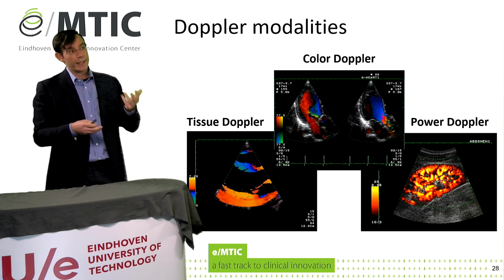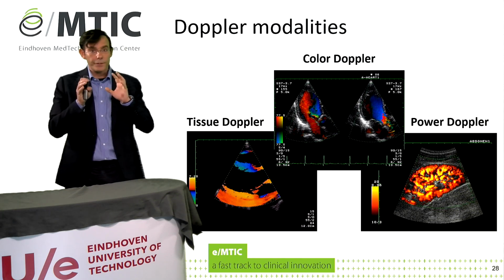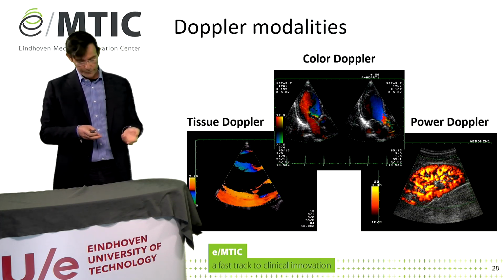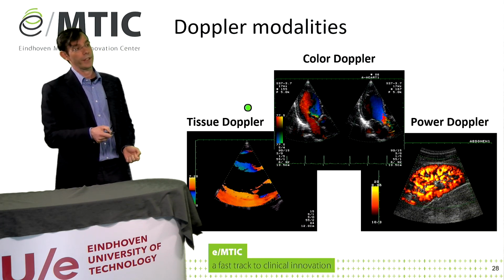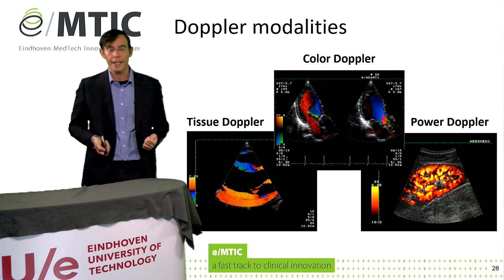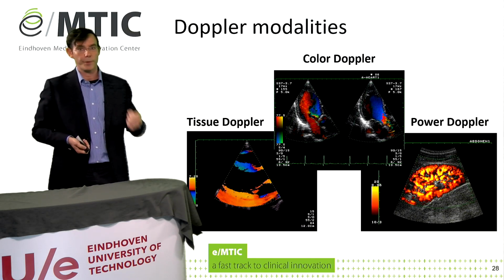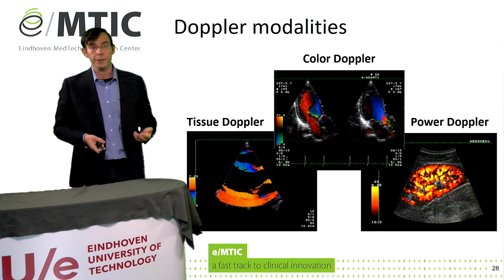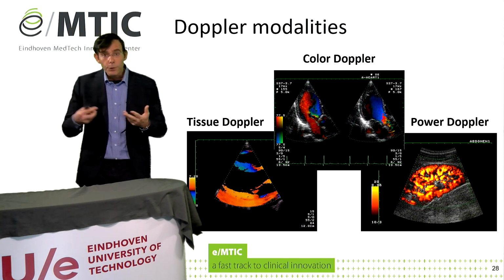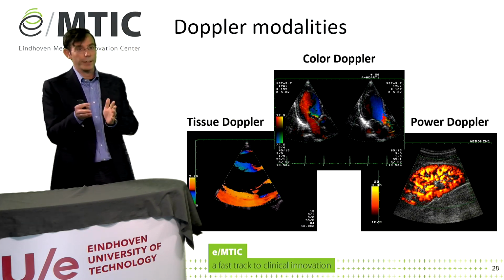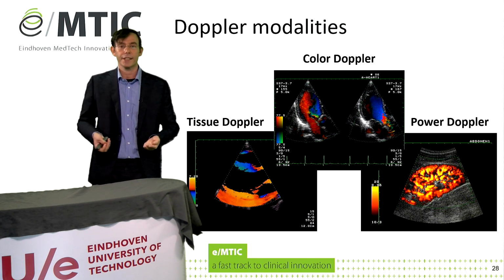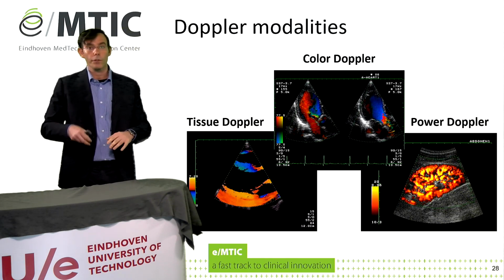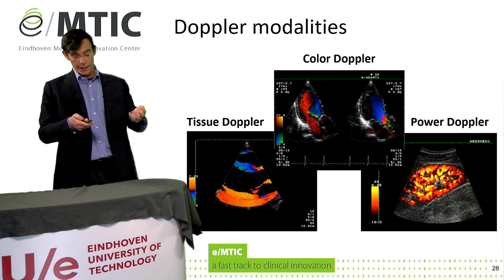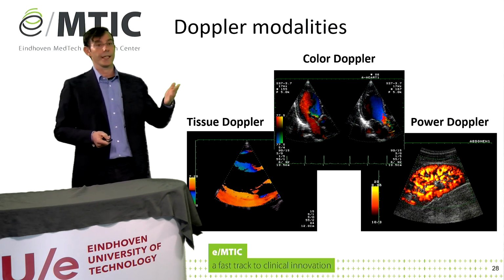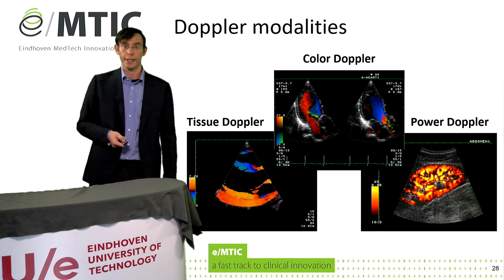You can also set up the filters in a different way and therefore focus on slow-moving structures, like for instance with tissue Doppler. And this is a great solution in order to image tissue motion. And even further, you can integrate the full Doppler spectrum rather than looking at the frequency shift, and then generate images that are very sensitive to low flow and can be used for looking at perfusion. And here you see a nice example, for instance, of renal perfusion.